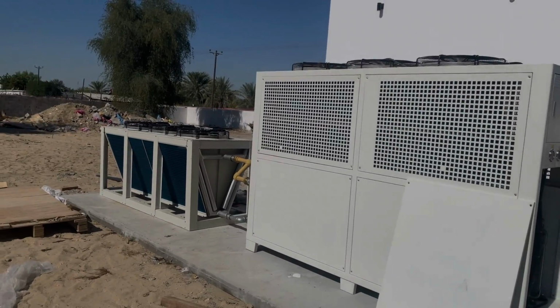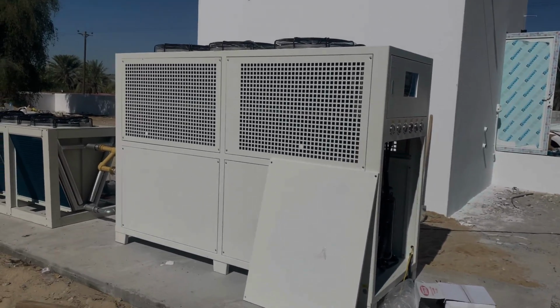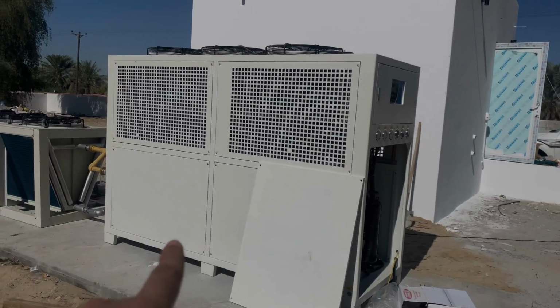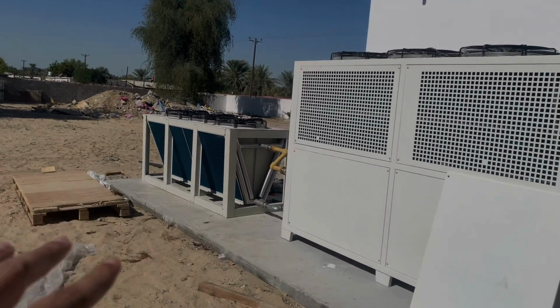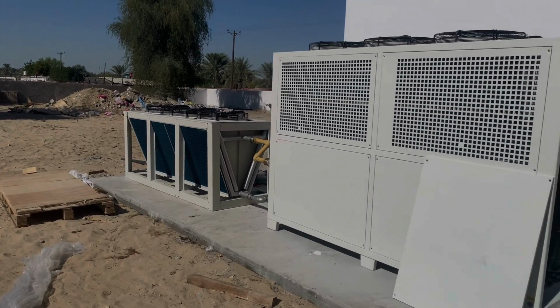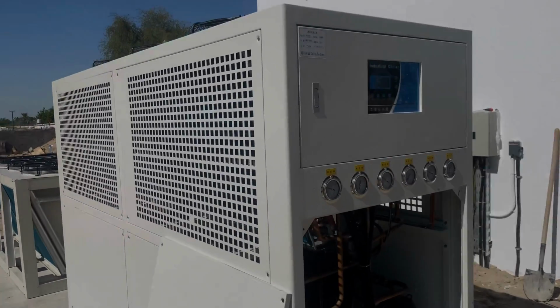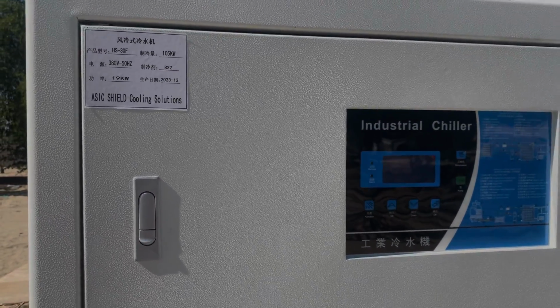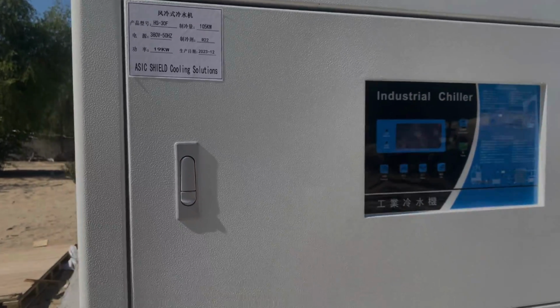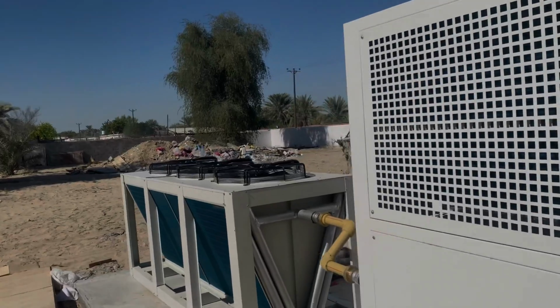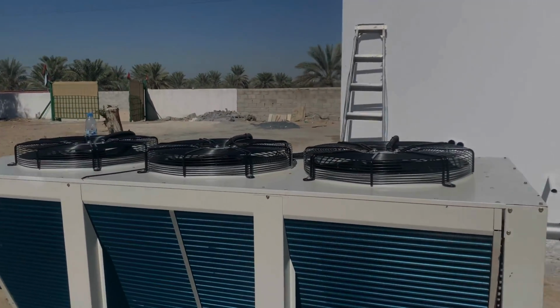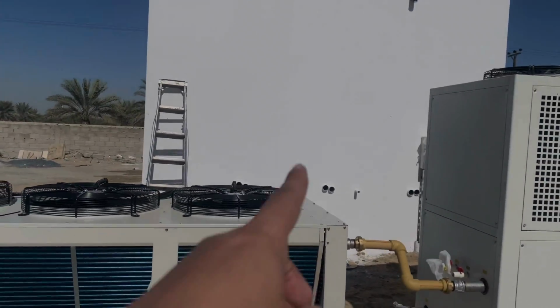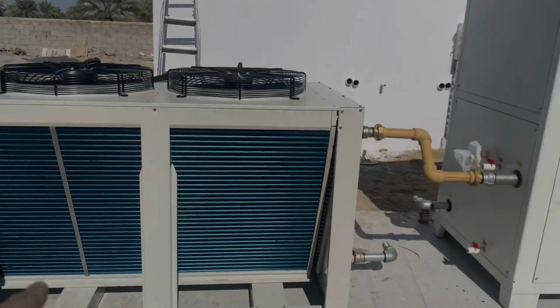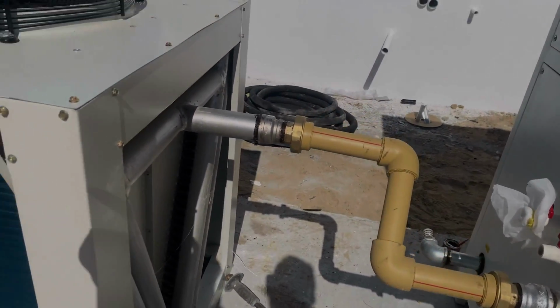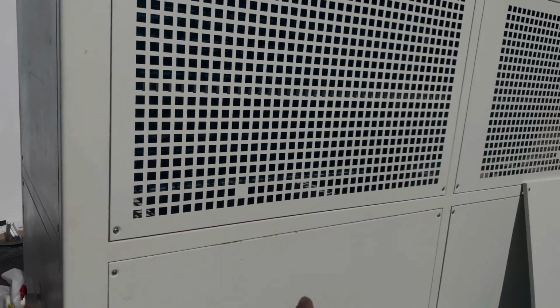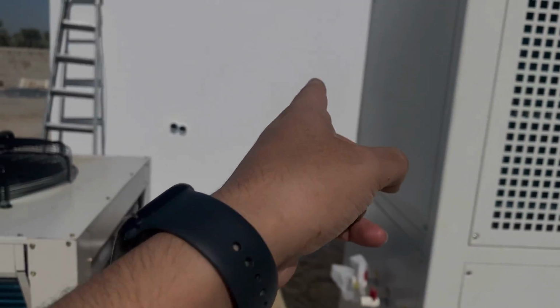So what we have right here is the cooling side of the system. Because it's really hot in the UAE, it requires a chiller, and we have a dry cooler which we can use during the cool season. Right here we have a 30 HP chiller, and right here is the 120 kilowatt dry cooler. The idea is to bring the water from the cabinet, go through the dry cooler first, and cool it down a bit, and then send it to the chiller, and then go back to the cabinet.